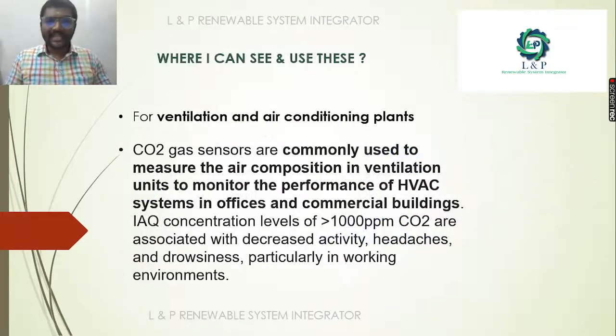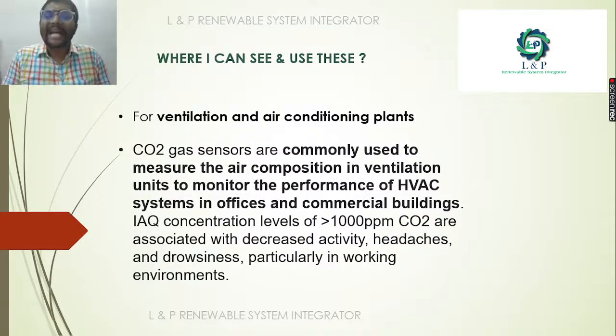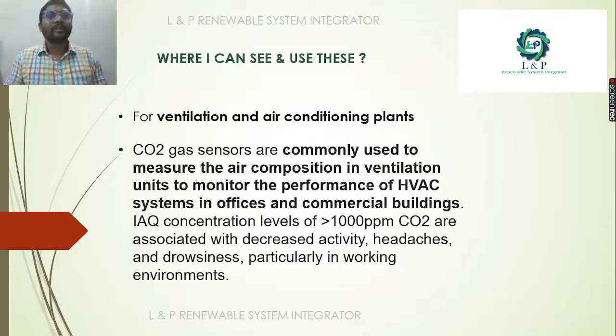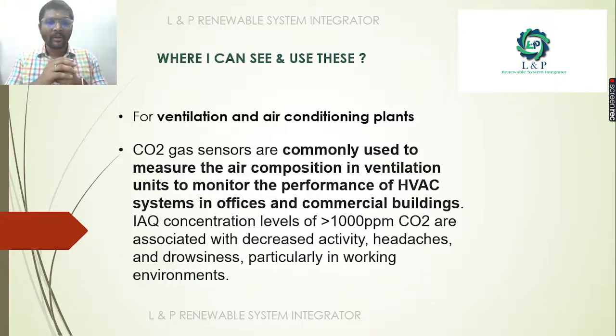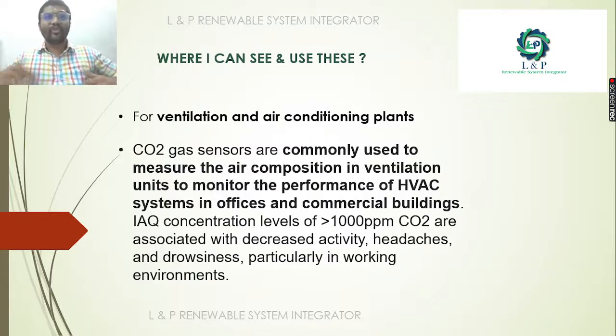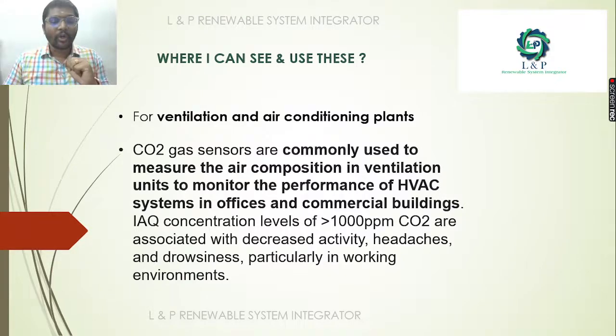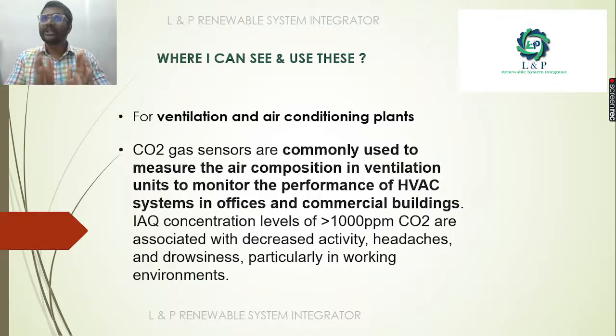Why do we want to use CO2 gas sensors in the heating, ventilation, and air conditioning system? Because people who are working in offices and commercial buildings need to concentrate and work. They should feel very comfortable when working inside offices. So CO2 monitoring is very much important, because we need to maintain the CO2 level less than 1000 PPM.